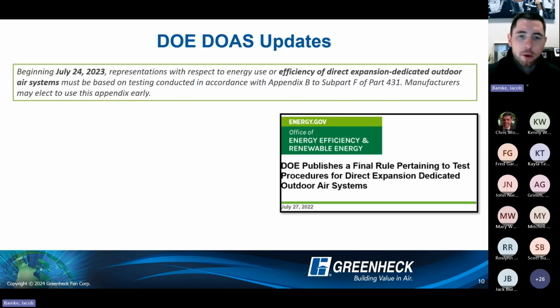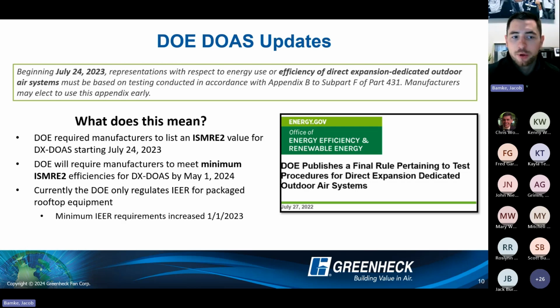So where this all comes from: the Department of Energy right now only regulates IEER. So as a manufacturer, all of our products have to be listed with a minimum IEER that meets those requirements. With DOAS, typically in the past, it's either been misapplied and they've been using IEER for a true DOAS type system, or nobody was really looking at it. And what happened was, July of last year, they started requiring manufacturers to list an ISMRE2 value for all DX DOAS equipment. And then actually today, they were supposed to really require a minimum ISMRE2 value. They don't have their compliance management system built out quite yet, but that is something that they're working on.